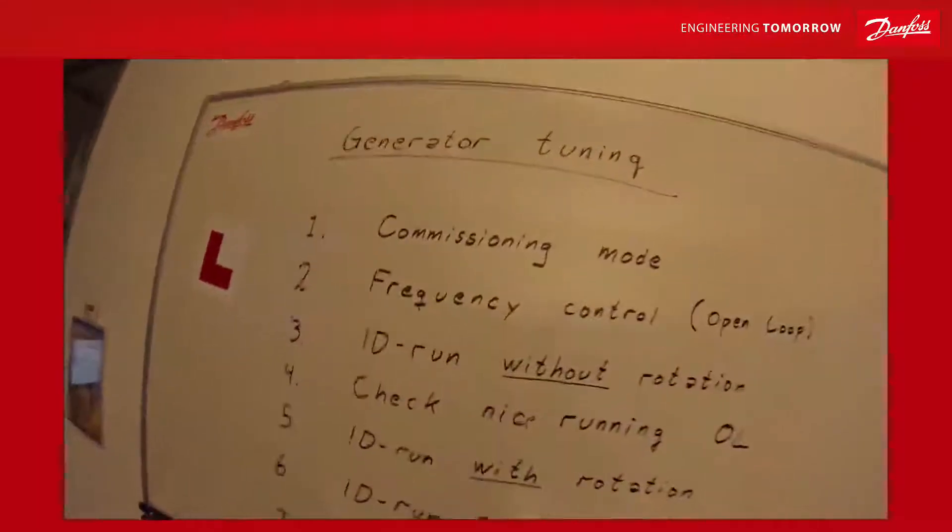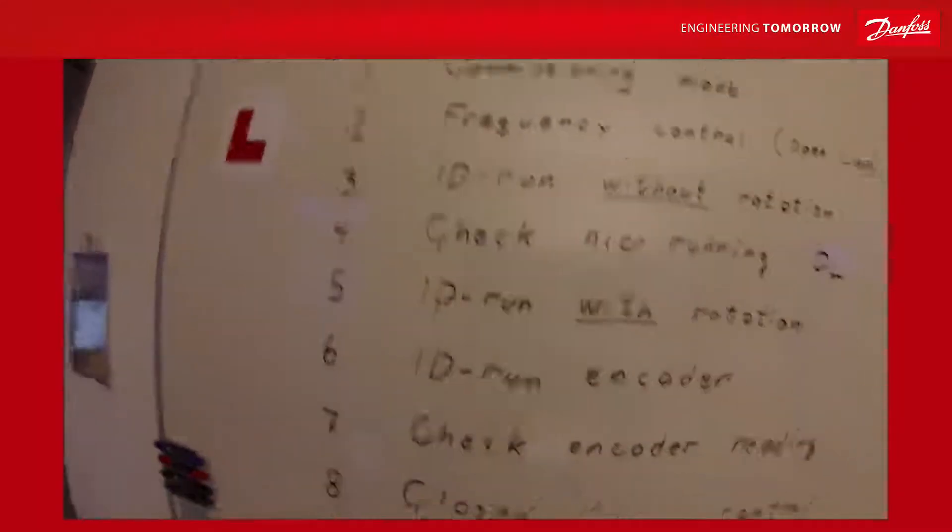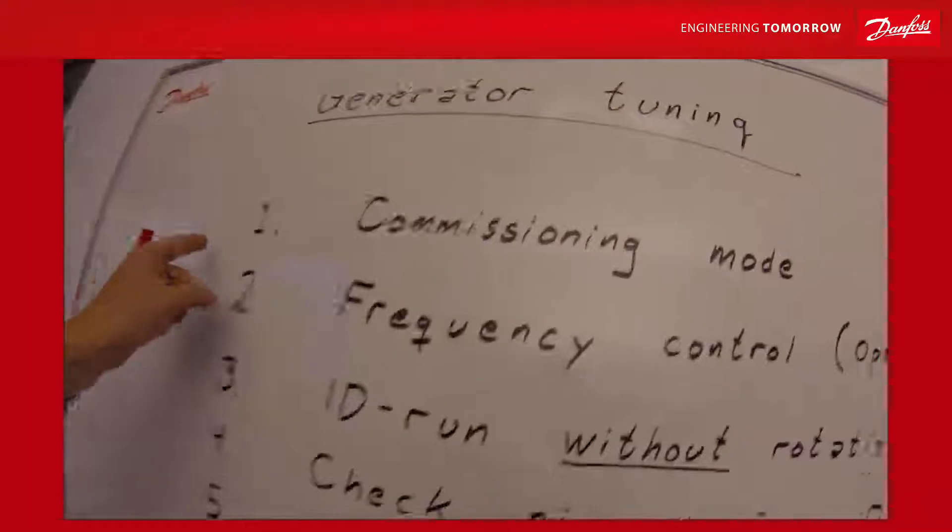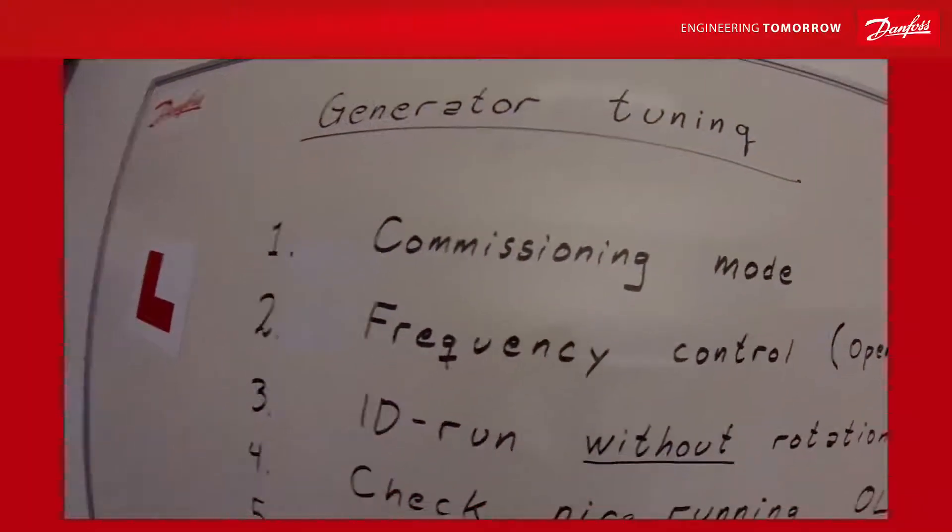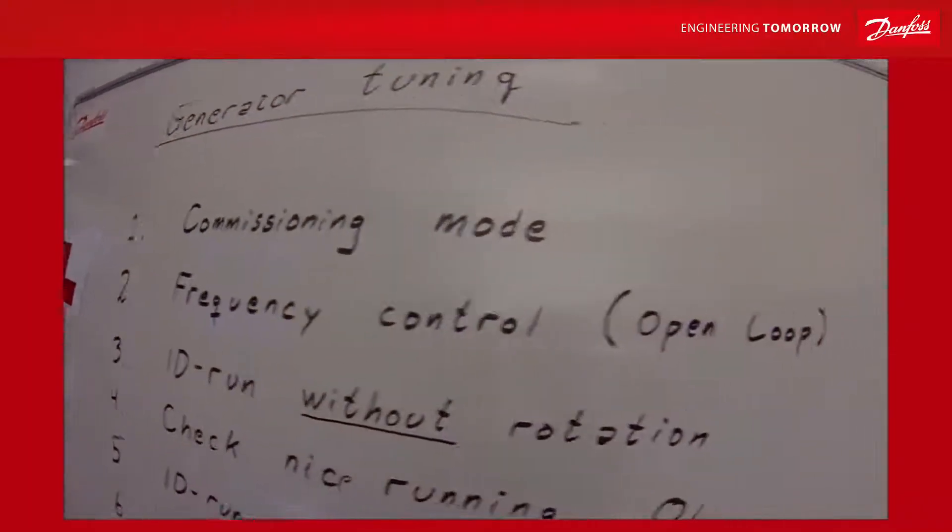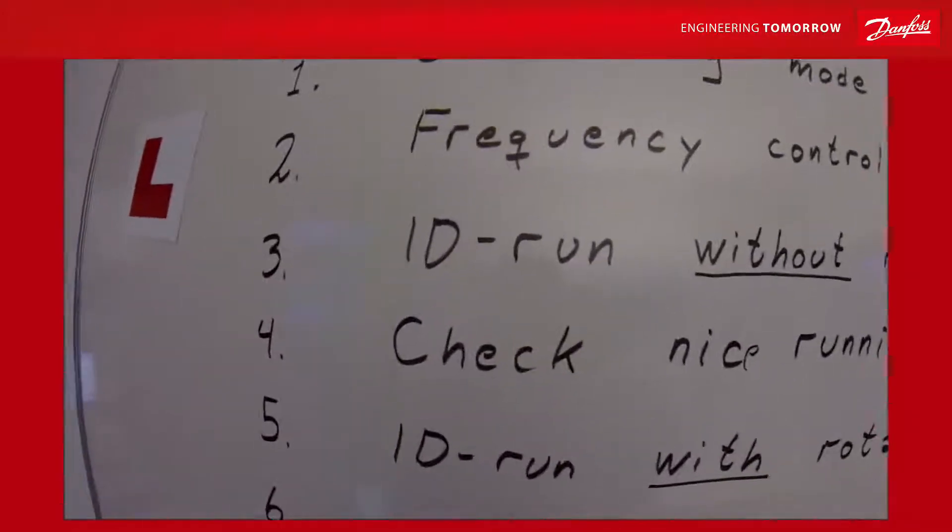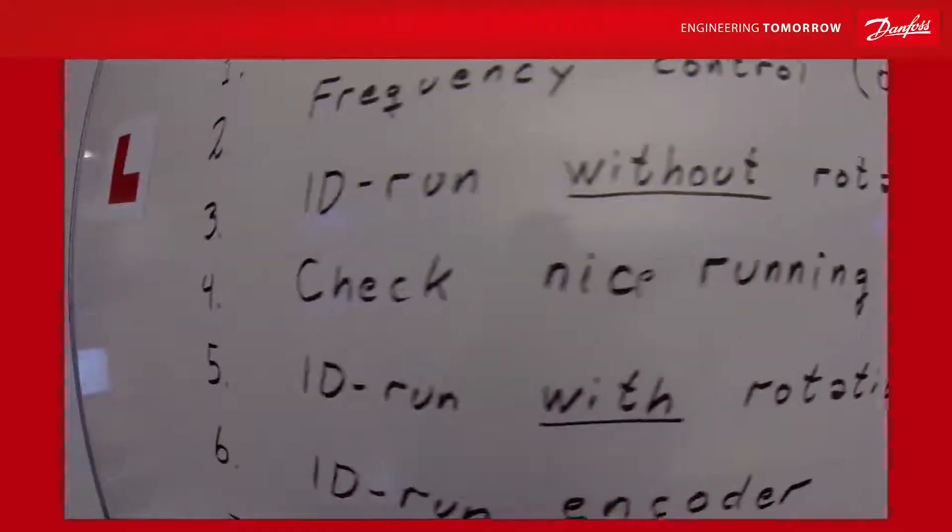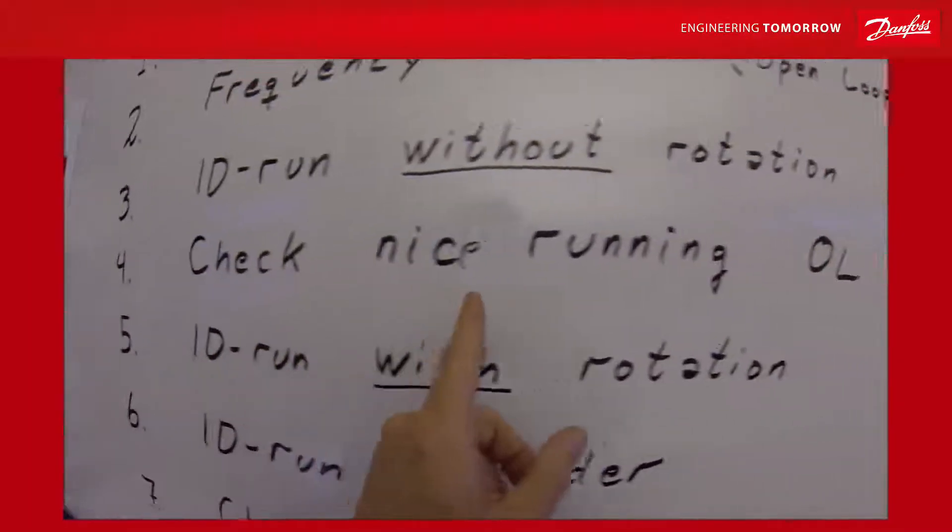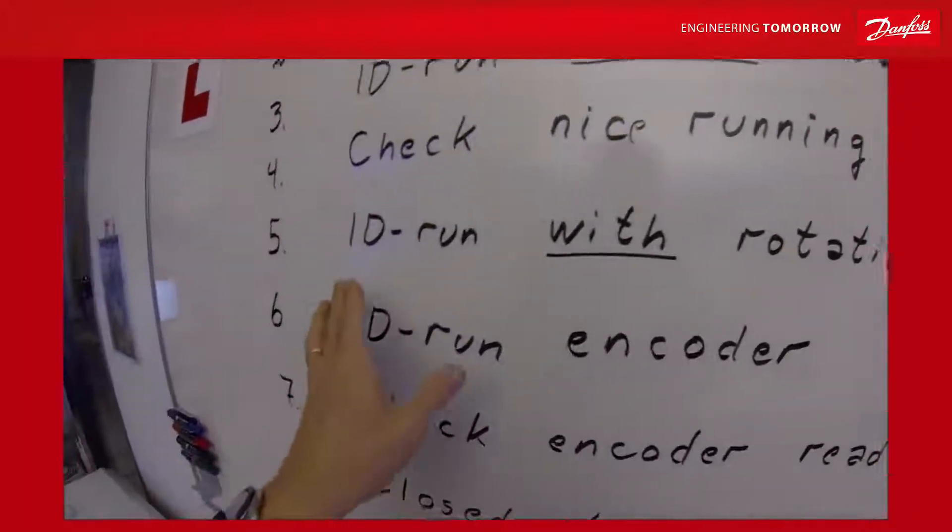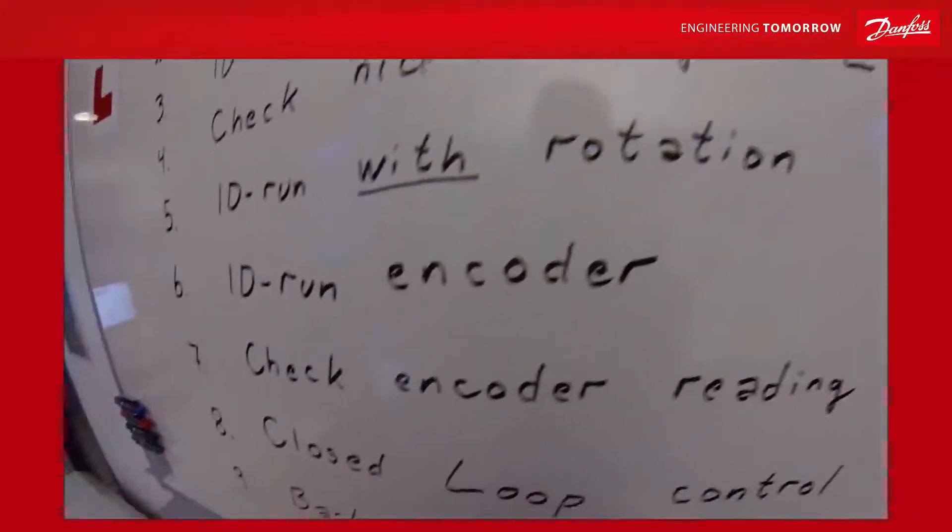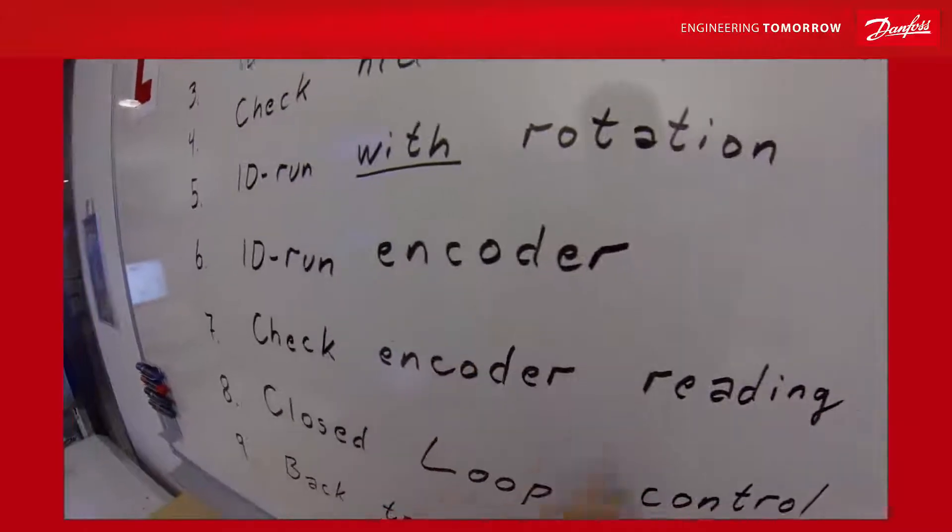The tuning of the generator involves these steps. We start by putting the drive in commissioning mode, then to frequency control mode because the open loop is not tuned yet. First, we do an identification run without rotation. We check that the motor runs nicely in open loop, then we do the identification run with rotation.